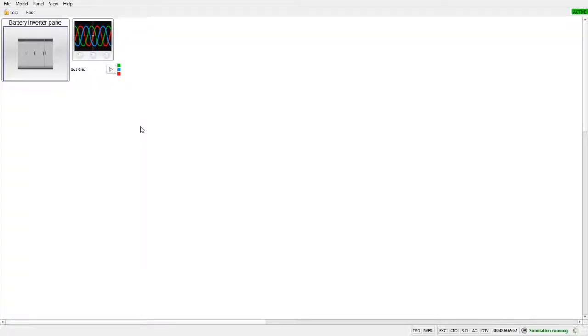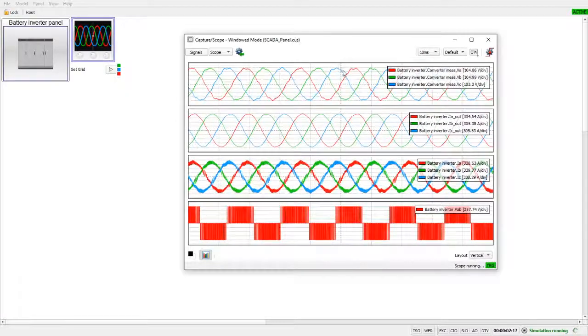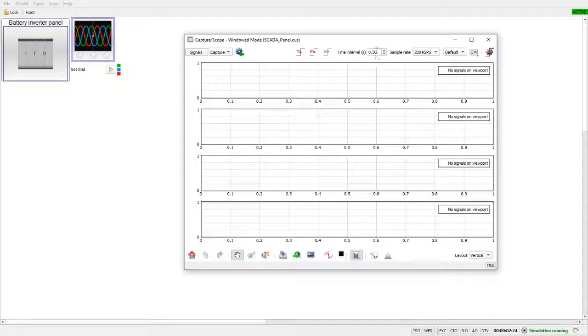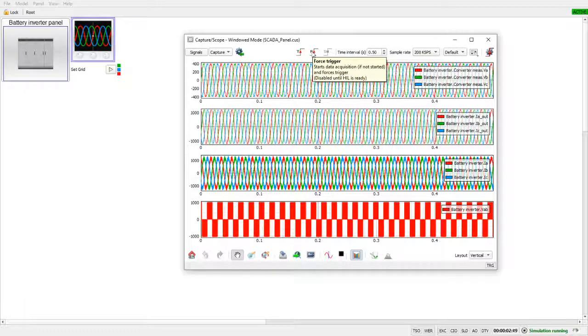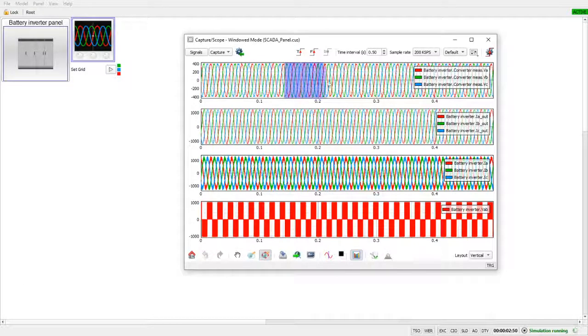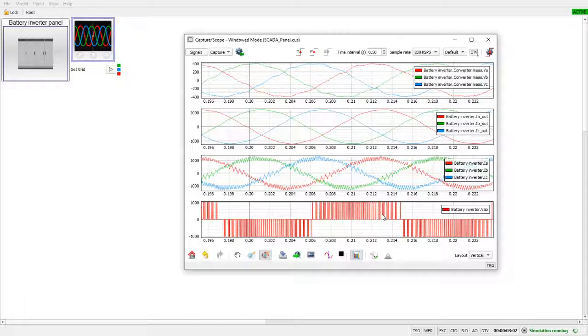There is also the possibility to see instantaneous values for voltage and currents. There are two modes: Scope and Capture. Let's capture for 0.5 seconds. By clicking Force Trigger we can force the capture. Let's zoom in — we can see switching ripples in our current as well as the voltage outside of the inverter.